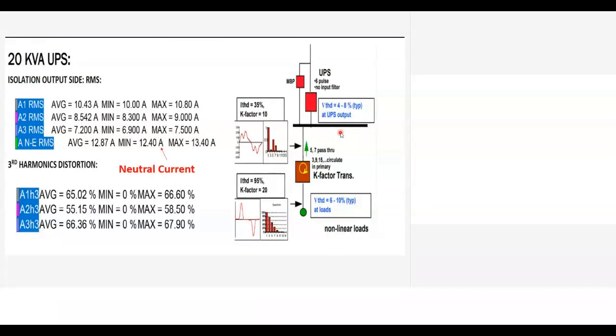So this is for a UPS where we installed an isolation transformer with a zigzag output, isolated, and also with a zero sequence impedance transformer, or neutral compensator. It's also called a neutral compensator. If you see the loads on the 20 kVA UPS, the loads were less, 10 amps and 8 amps and all that. But if you see the third harmonic current, you will find that it is very high, at almost 65%.